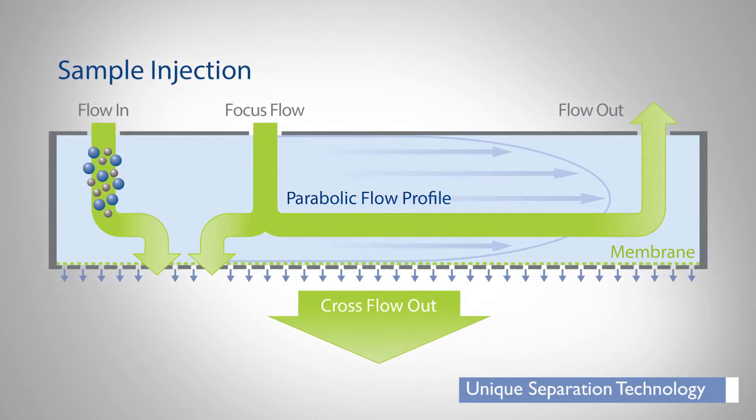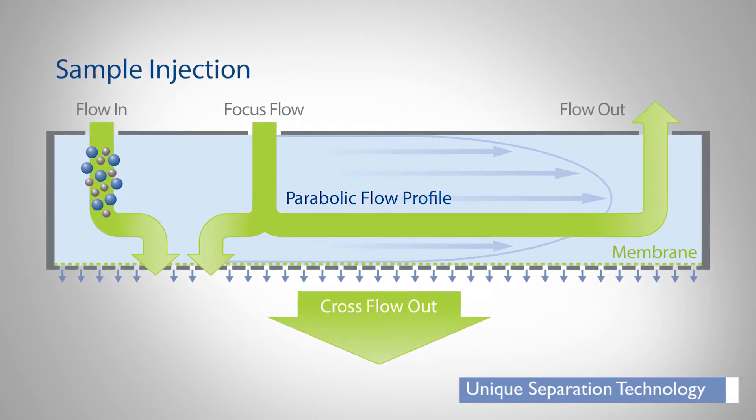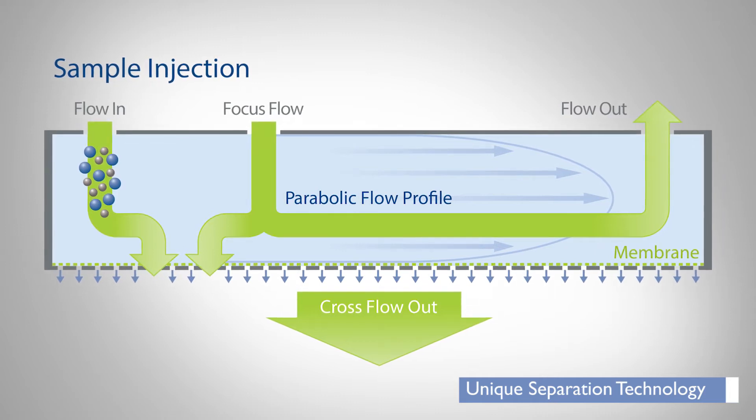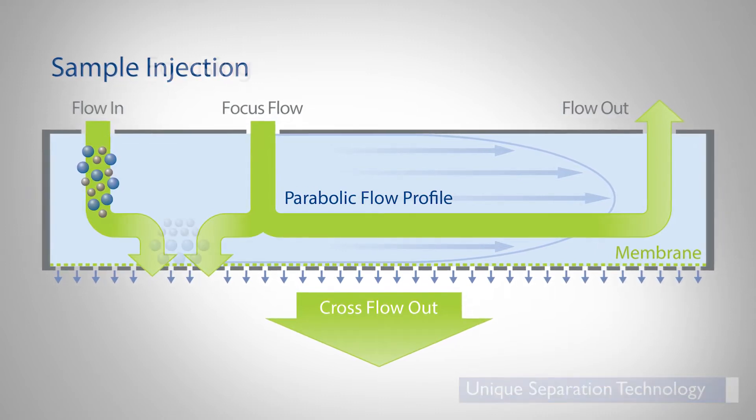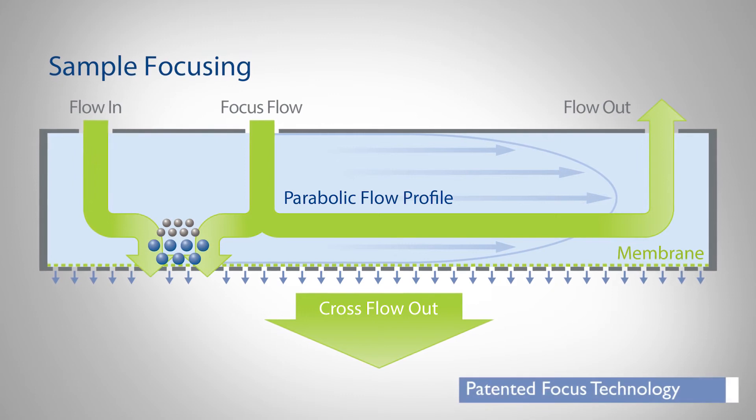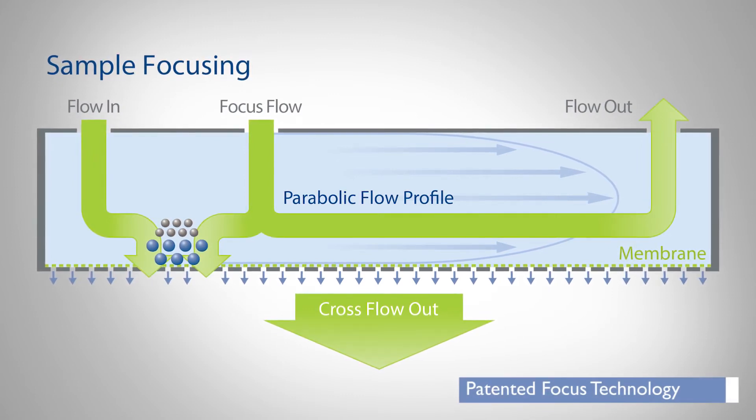Sample and main flow are delivered into the channel by the eluent pump, while at the same time the focus flow is established by the focus pump. During the focusing step, the sample is accurately positioned in the channel for optimum resolution.